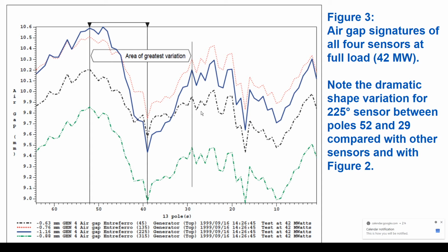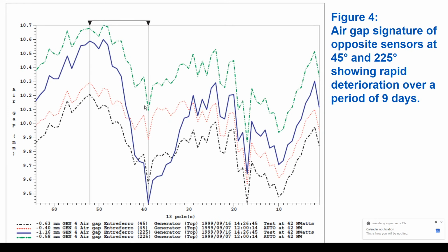Okay. So what we were able to determine is that this unit had a rim that is not properly supported, and as we increased the load, the rim was actually slowly being pulled off of the spider. Okay, so we were able to prevent this from hitting the stator, and at the same time we were able to confidently assume that this is what happened on unit number 2. This section actually came off and hit the stator core. You can see how bad this section is. Remember, this is the same reading, okay, but this sensor was seeing a much greater anomaly than the other sensors.